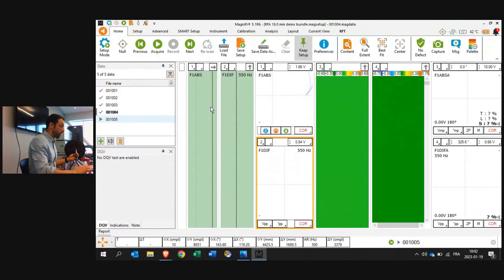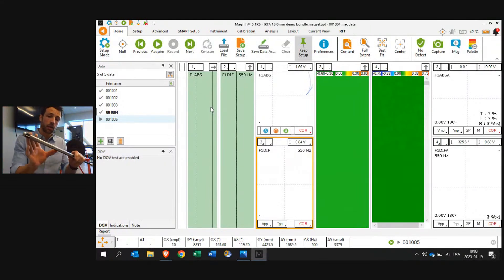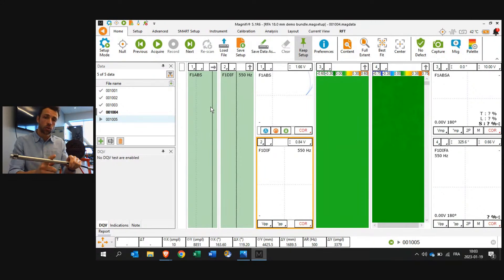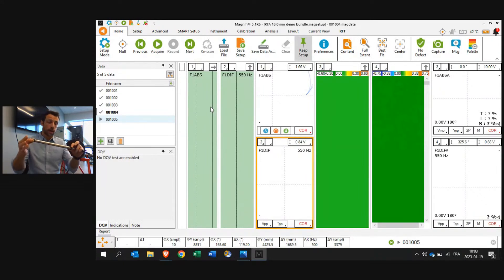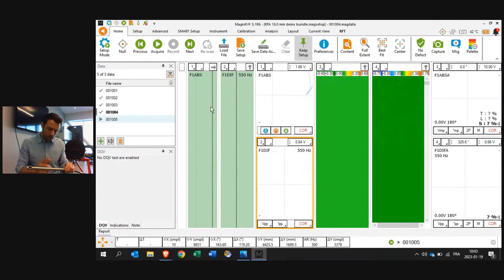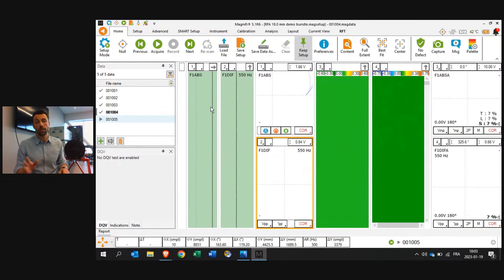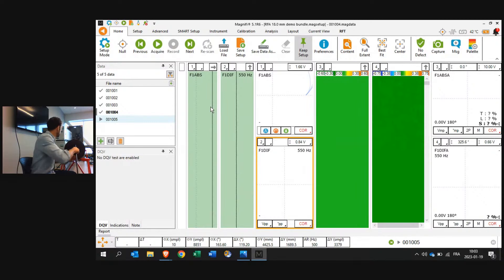Now switching to Magnify 5.1 with the RFA Pro. The big difference in this probe is we have a dual driver configuration, and in the middle we added two rows of array coils to give us a C-scan. With a C-scan, we see the defect morphology, leading to better sizing curve selection. We have new centering devices offering a higher probability of detection of smaller pitting. We've kept the same fill factor, cleaning requirements, and pulling speed as conventional RFT — so there's no difference in operations.